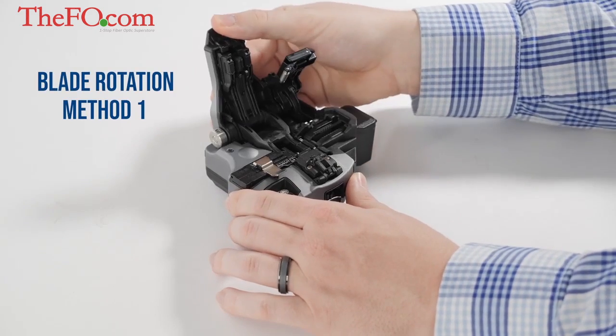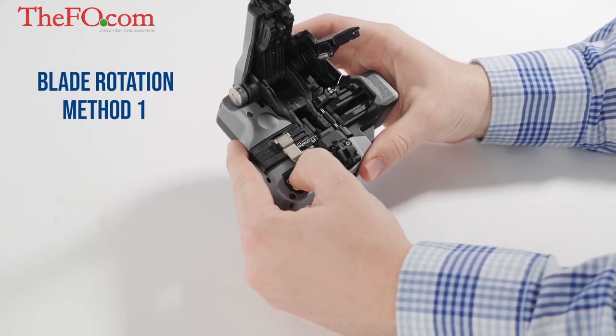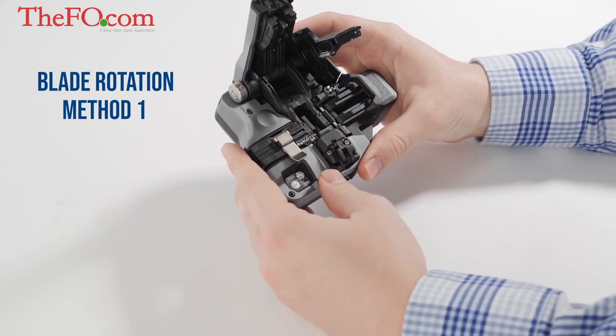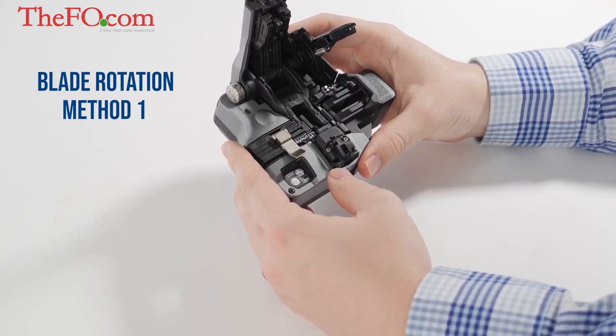Use a dry, lint-free cotton swab with the same cleaning motion to remove excess alcohol and any remaining loose debris. If cleaning the cleaver does not eliminate cleaving problems, or if the cleave count is high, it may be time to rotate the cleaver blade to the next position.